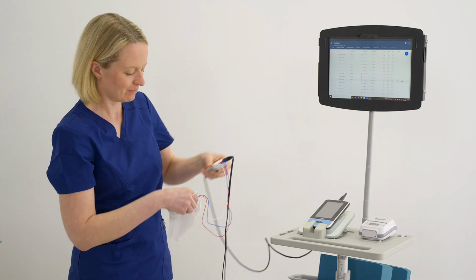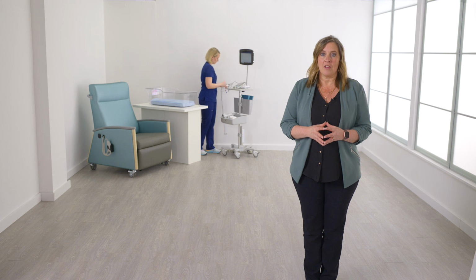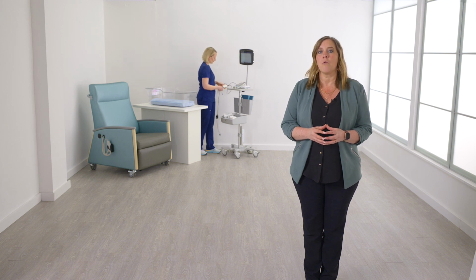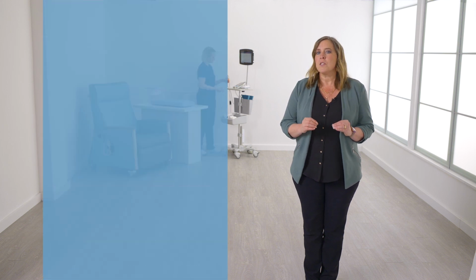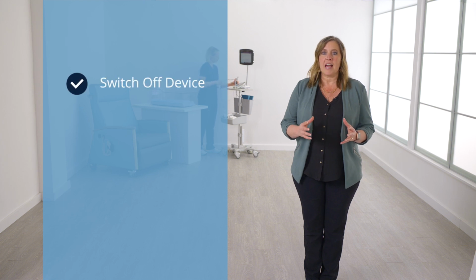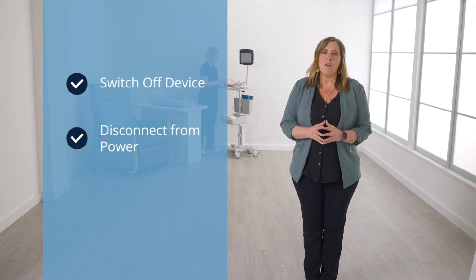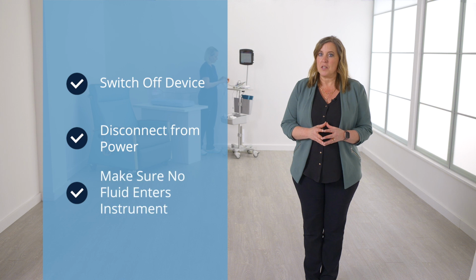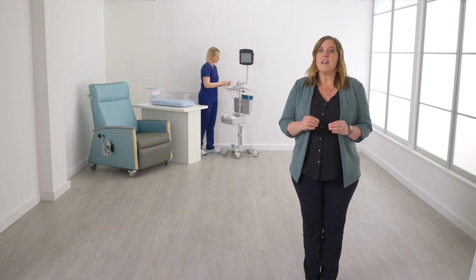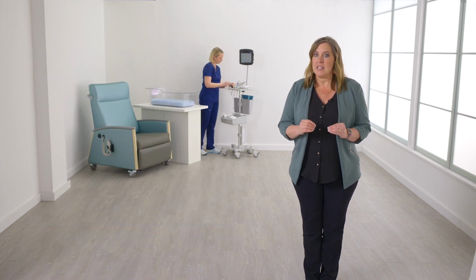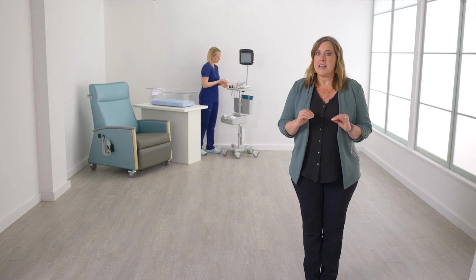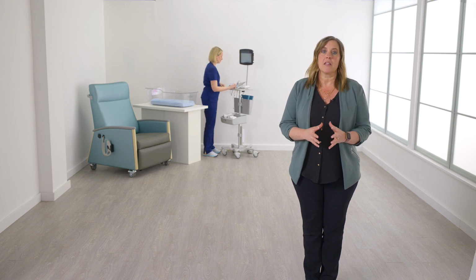The surface of the Novus instrument may be cleaned using a soft cloth moistened with a mild solution of water and detergent. Always switch off the device, disconnect from power, and be careful that no fluid enters the inside of the instrument or the accessories. These recommendations for cleaning and disinfection of the Novus are not intended to replace or contradict the policies or procedures required for infection control by your facility.